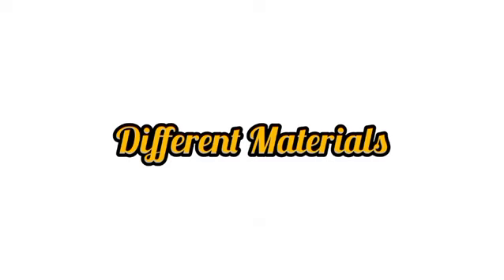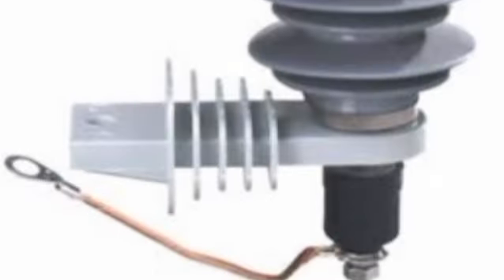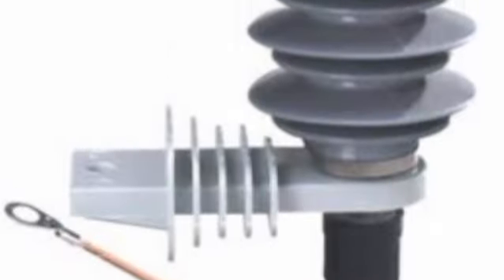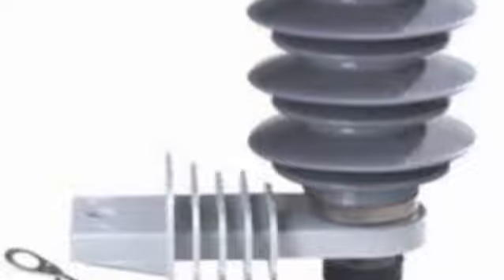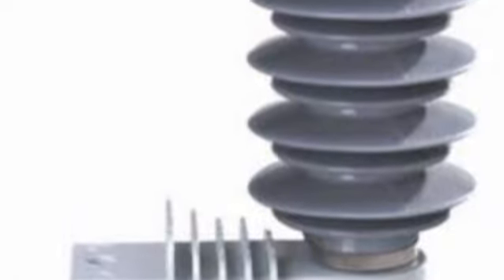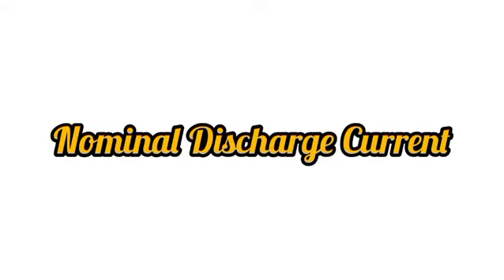Different materials. The main material of the lightning arrestor is zinc oxide, a type of metal oxide varistor, while the main material of the surge protector varies according to the surge resistance level and graded protection, and its design is much more precise than ordinary lightning arresters. Nominal discharge current.